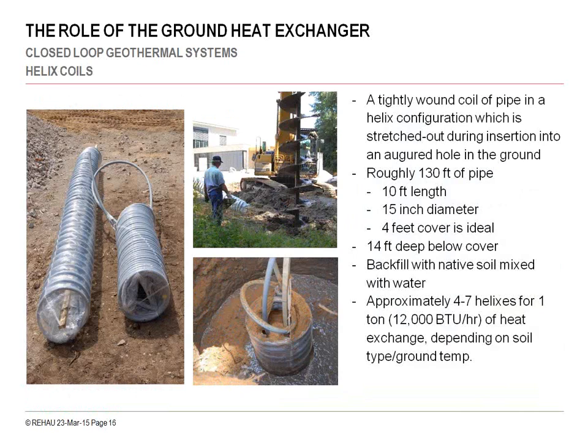This is a helix coil, and this is a cost-effective installation where we are using an auger bit and going down about 14, 15 feet. You can see the image on the left, you can see it stretched out. This is somewhat like a slinky. You stretch it out, and we're getting about 130 feet of pipe down in each boring, and then these would be tied together in a series, and they're spaced out about 10 feet apart. And depending on the location and the temperature and the type of soils, you have anywhere between 4 to 7 of these together in a series to generate a ton or 12,000 BTUs of heat exchange.